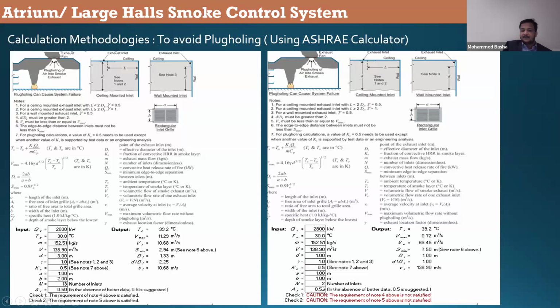And the number of inlets. What is number 5? It is telling Vs must be less than or equal to Vmax. Now, if I am using 2 inlets only, each is taking 69.5 meter cube per second. So the combination of 2 will be higher than the original volumetric flow rate I need to take, which is 138. So which is not acceptable.